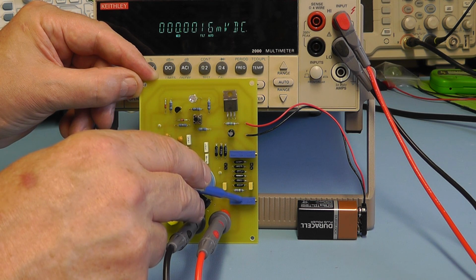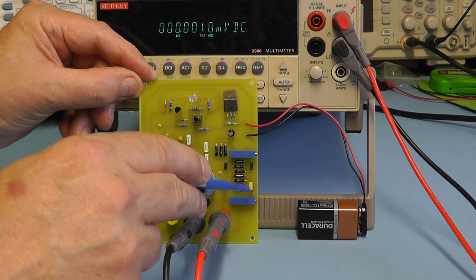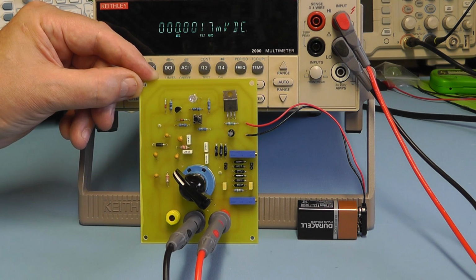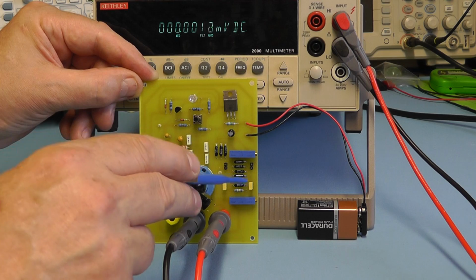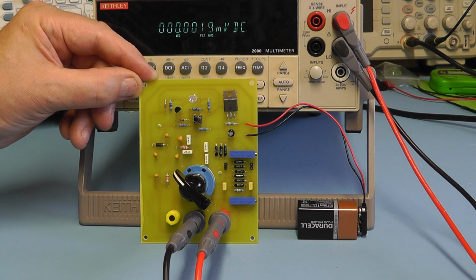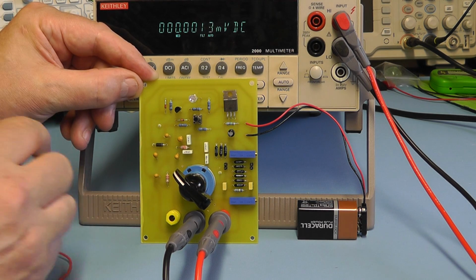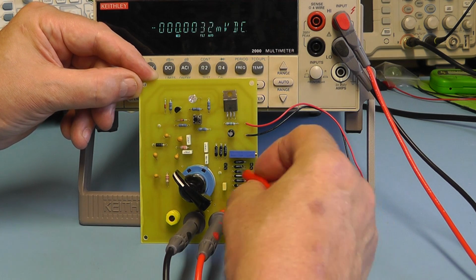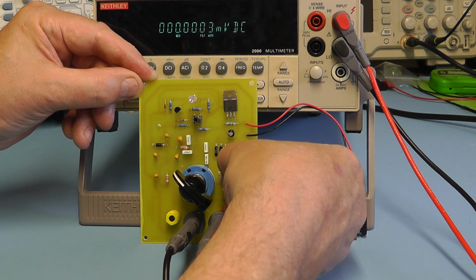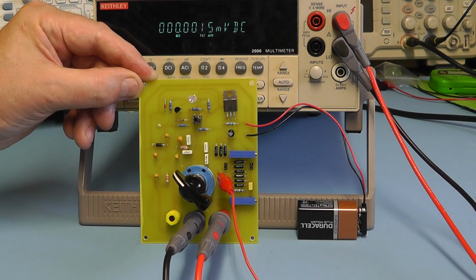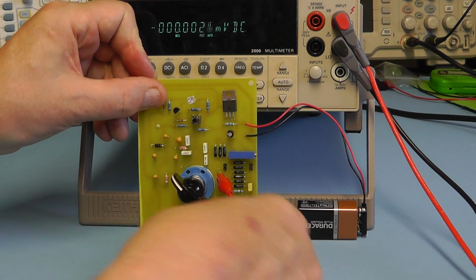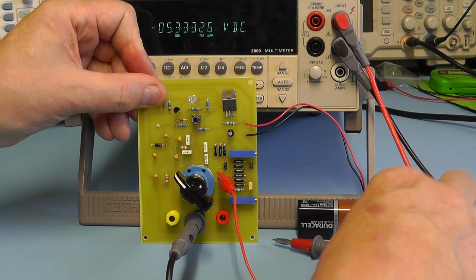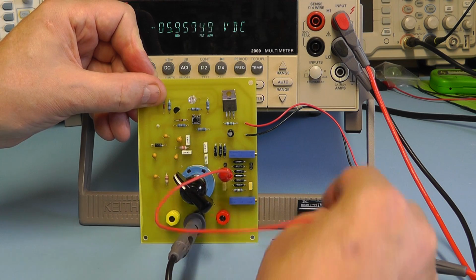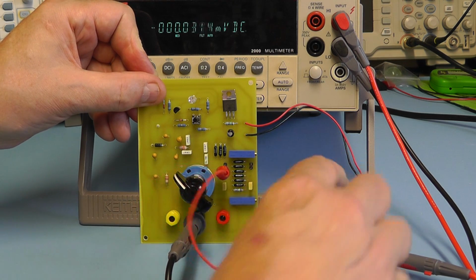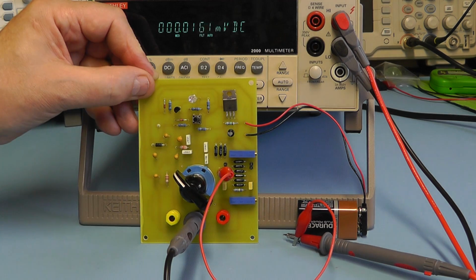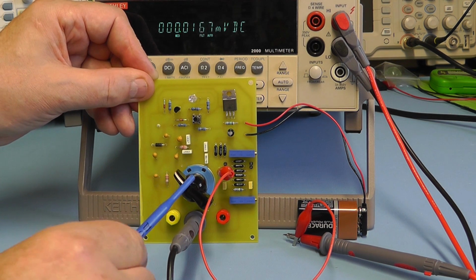And this time we're going to set it again to half of the 10 volts, which we noted before, which was 5.3026. But this time we're going to connect the positive lead of the meter to the 100 millivolt calibration point, which is just there. There's a pin there. So I'm going to remove the lead and then just clip onto it there like that. So that's set now to 100 millivolts.